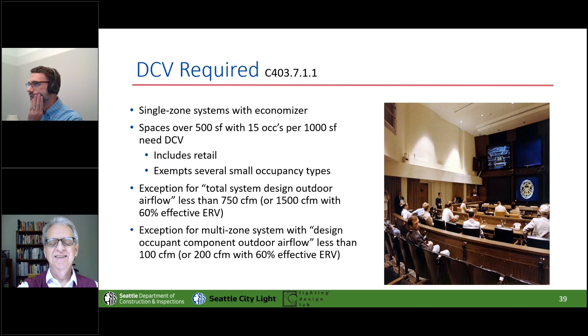Yeah, so we did this in the last version. This shouldn't be a surprise to anybody if you've been watching these in the past cycles. But the difference between what we conventionally would do for an office building way back, like a VAV system: you would introduce outside air to the return air path, you pull it out of the space, you'd pump in outside air, you'd mix them together, you'd reheat or recool that and put it back into the space. So you're essentially using air to move a bunch of energy. And that outside air mixing in could be good in some cases, but could be bad when it introduces more humidity than you want. You can't deal with it directly. Now you're dealing with it in a much larger airstream, things like that.